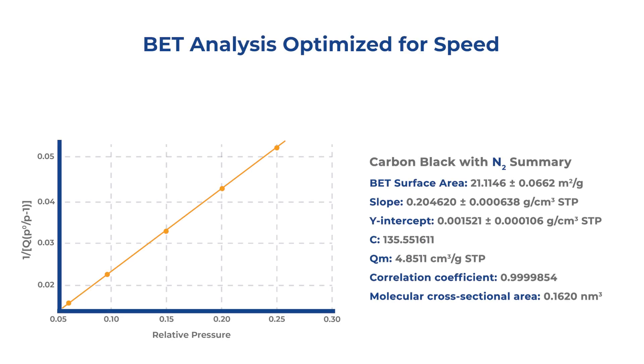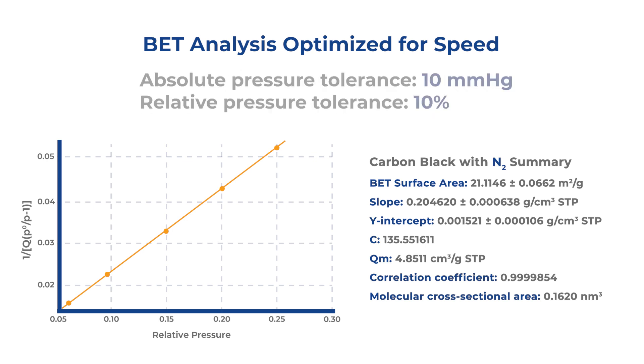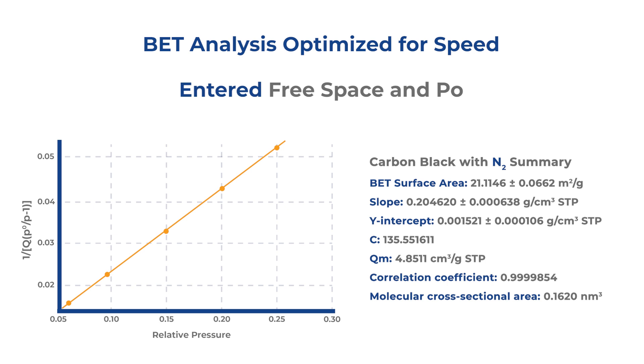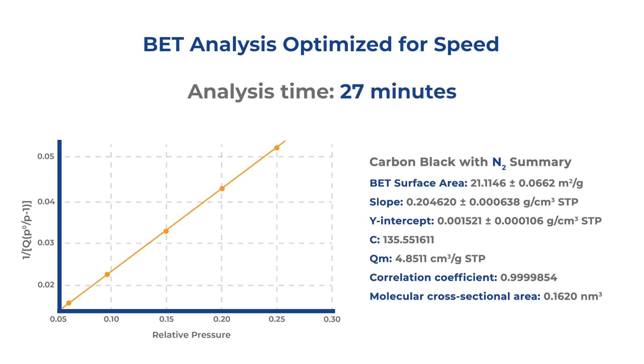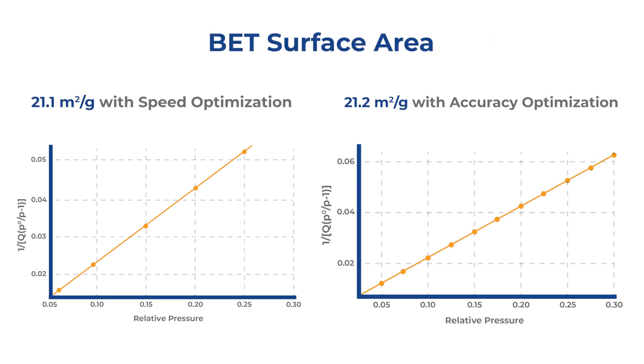Here is an example run optimized for speed with the same sample. Five points were collected and the pressure tolerances were increased. The free space was entered from the previous run since they were the same sample, and the saturation pressure was entered. The equilibration interval was shortened to five seconds. Under these conditions, the analysis time was shortened to 27 minutes. The BET surface area was 21.1 with speed optimization and 21.2 with a normal run, so there wasn't much compromise on the quality of the data on this particular carbon black sample.